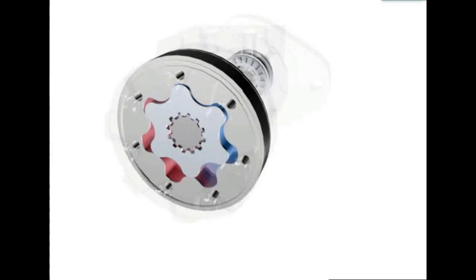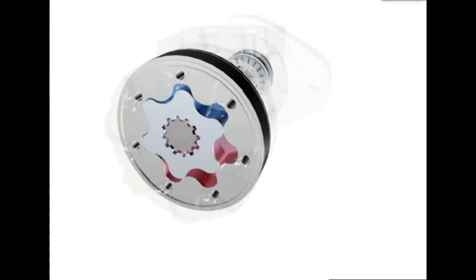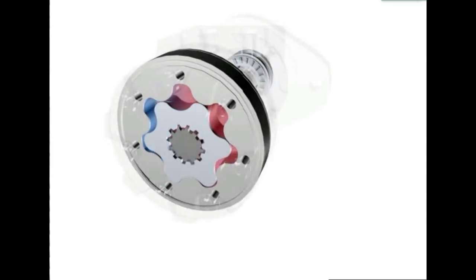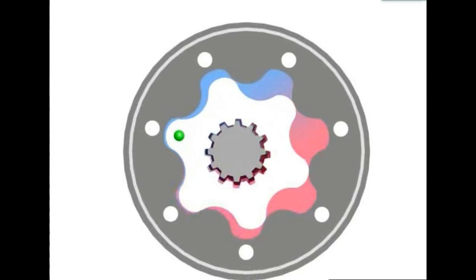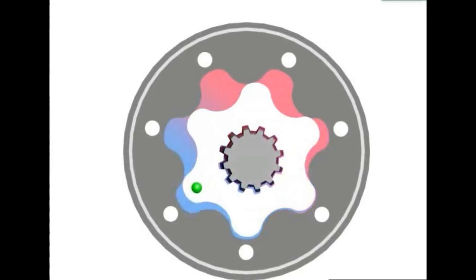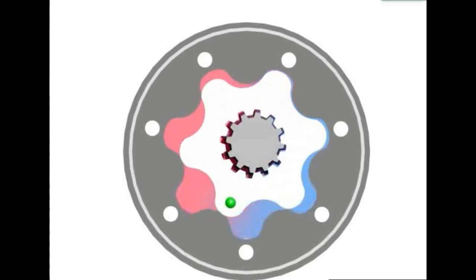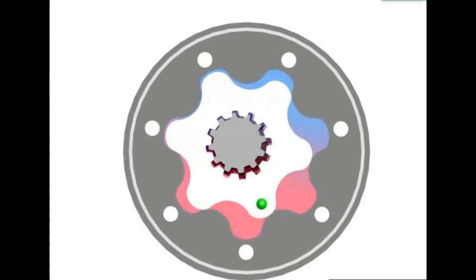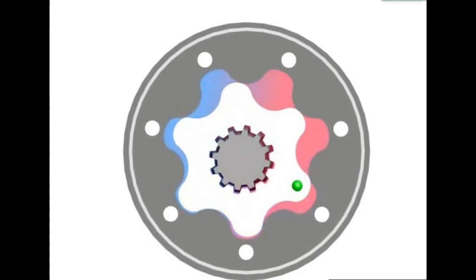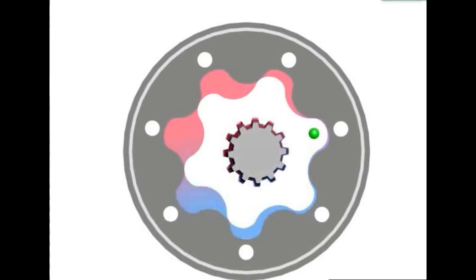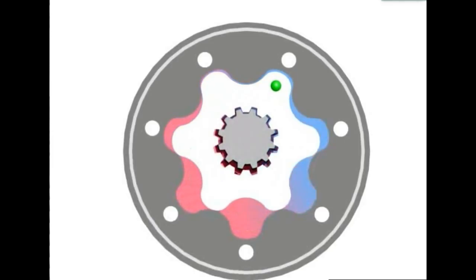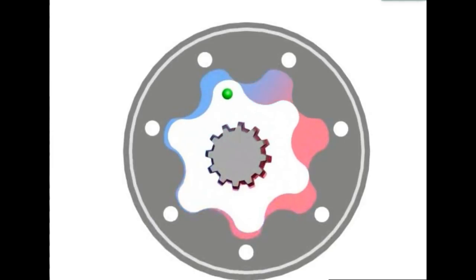As the rotor moves, the next rotor tooth and stator tooth oppose each other. The rotary valve allows fluid to enter the high-pressure cavity in its new position, and the cycle begins again. These cycles cause the rotor to orbit around the inside of the stator. For each orbit the rotor makes, the rotor rotates one tooth in relation to the stator. Since this stator has 7 teeth, it takes 7 orbits of the rotor to complete one rotation of the output shaft. This creates a 7-to-1 speed reduction and a similar multiplication of the torque output.